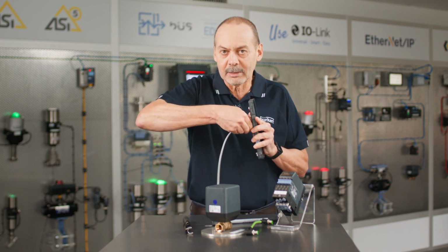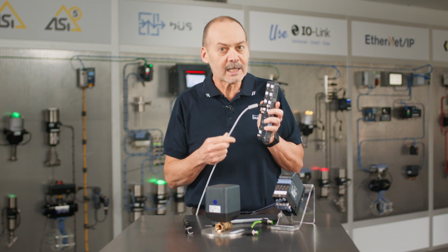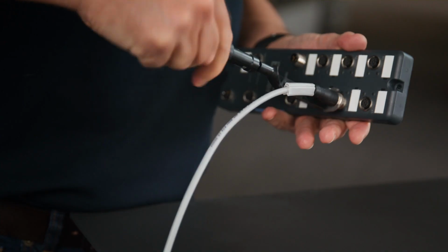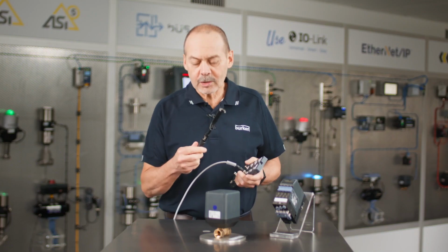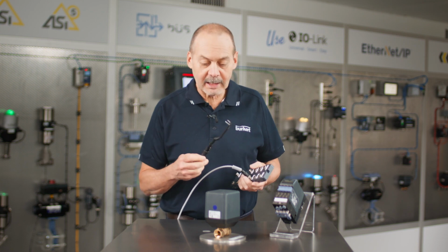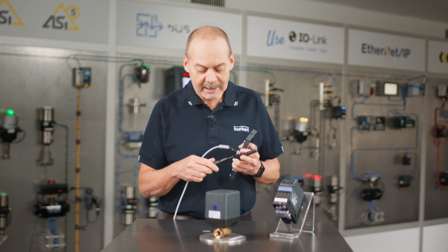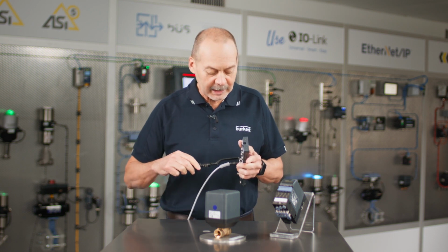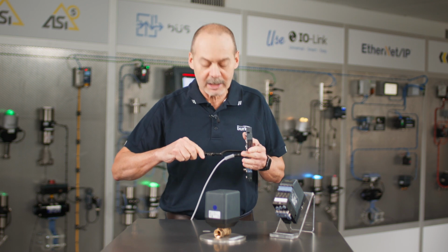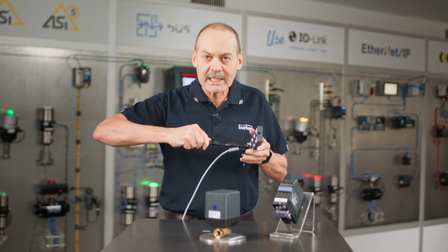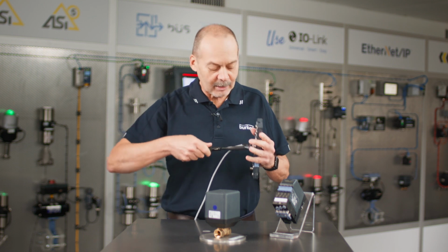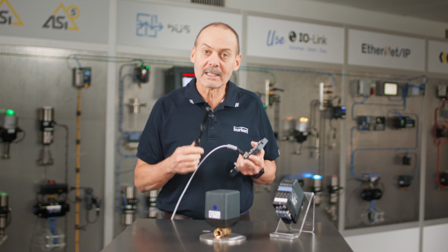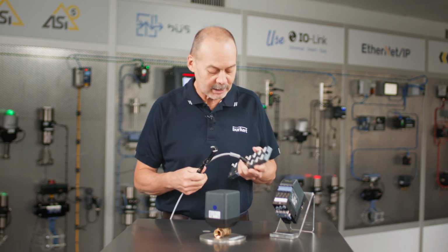I will never be able to undo that by hand. And in an industrial site, that's a good thing. So we know now to undo it, we have to undo it like that. Yeah, these little torque drivers, they are available from Bürkert, and they work with both M12 and M8 connectors. This one here is available from 0.6 to 1 Newton meter, and is specifically designed to go on most of the cables that you've got in the field. You will actually hear it click when it reaches the right torque. And you can of course adjust it down to 0.6 Newton meters if you're doing a plastic to plastic connection, as we spoke.